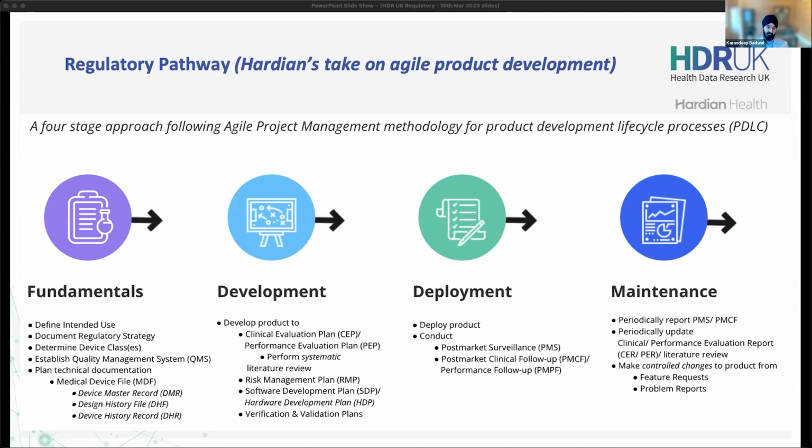What do I mean by post-market surveillance? It could be speaking to physicians, speaking to end users, questionnaires. Now, the more proactive approach with post-market surveillance is to look into things like literature, look into things like the FDA MAUDE database, and obviously EUDAMED, which is the European system, is currently in the works. But go out to see what your competitors are doing, see what the modes of failure are, and make sure your device doesn't fall victim to that effectively. So that's what you want to have for post-market surveillance.